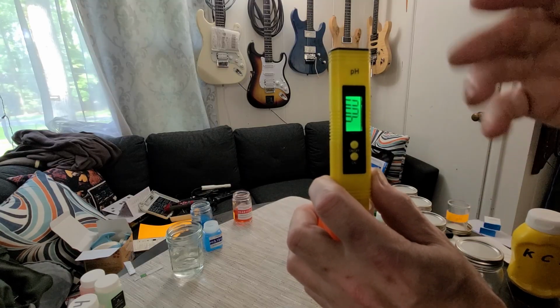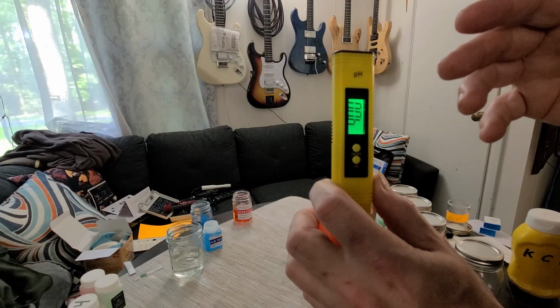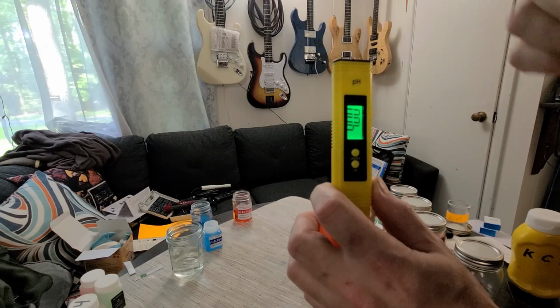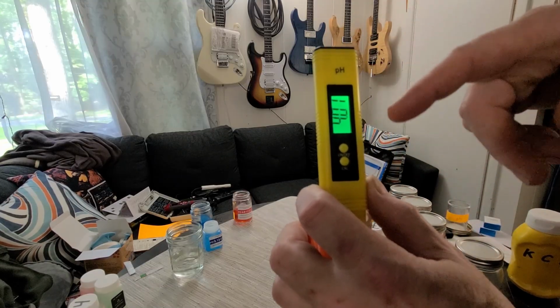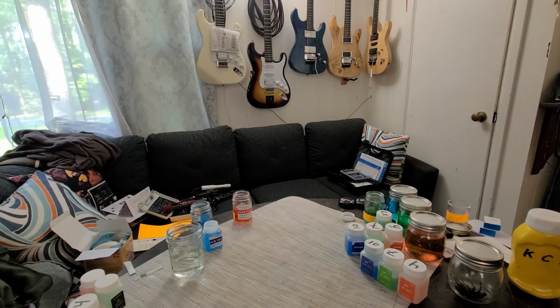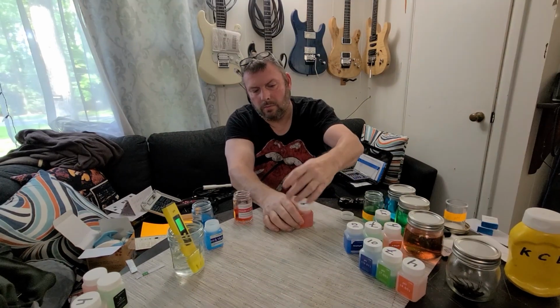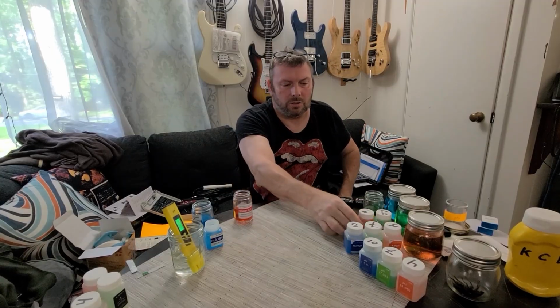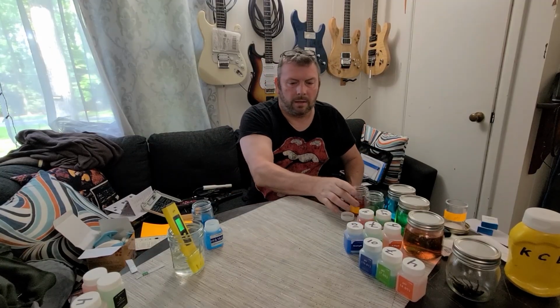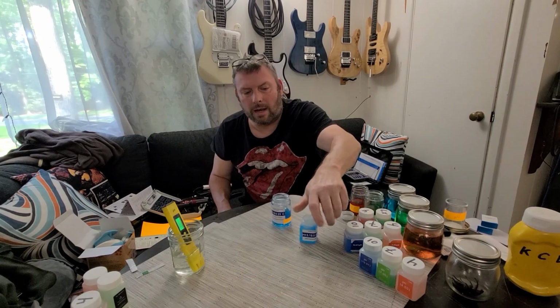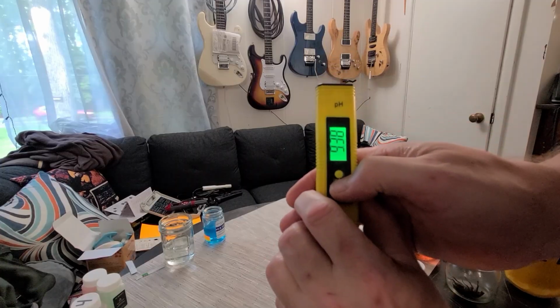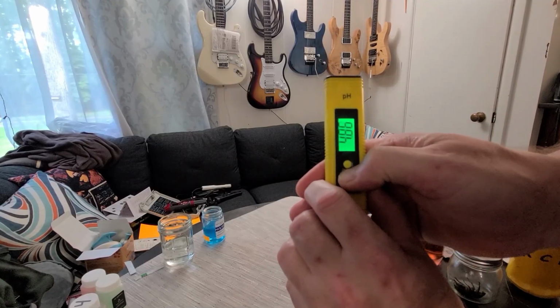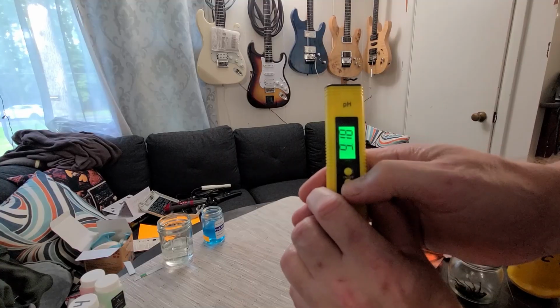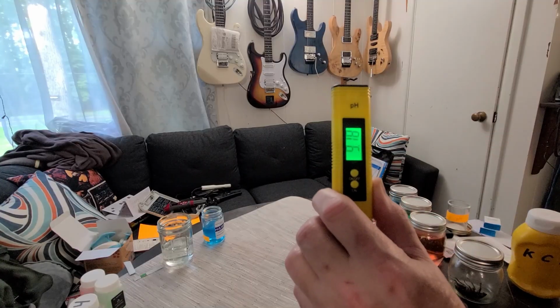After it hits this, it goes past 5 seconds, and it'll say 6.86. You got to press the cal button. You got to let go after your 5 seconds, and then you got to tap the cal button one more time to make it drop down to the 4.0. So now we calibrated 4.01. Remember, I have my caps matching my solution so I don't cross-contaminate. And then our last one, 9.18. I'm sorry, 9.18. I got my pre, then my... and 1, 2, 3, 4, 5. Nope, not 6. Nope, not 4. 9.18. So we're on the 9.18.